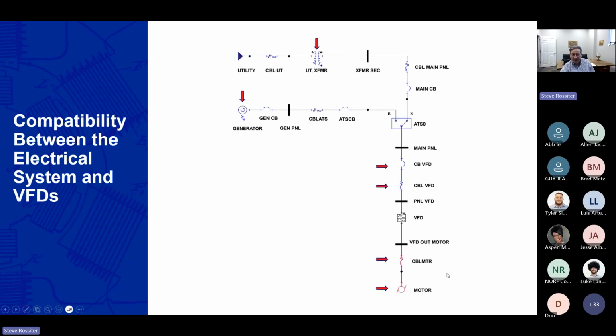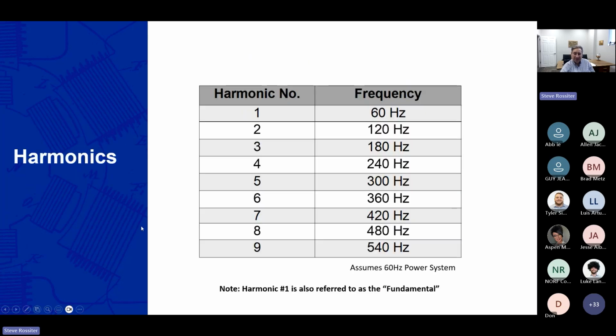And so we created an inverter duty rewind way back in the 80s, just because once you recognize the problem, there's always a solution. So to talk a little bit more about this harmonic on the line side, the cause of that, or what that's all about.